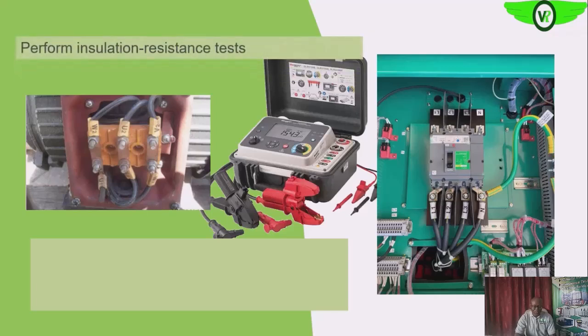In the insulation resistance test, what we are actually testing is the insulation between the phases. So we'll disengage these bars, okay, and test the insulation between the V and the U phase, and then the U and the W phase, W and the V phase. So you test the insulation between the phases here and then on the generator too. Since it is starred, it will be very difficult for us to test the insulation between the phases here. But if the star point is brought out, it's just for us to disengage like this now.